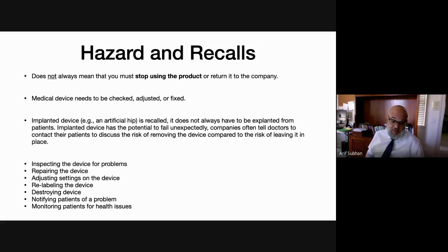So it's fine. If there's a problem, you go fix it. Then you need to repair it, maybe adjust it, or there may be an issue with a particular feature or particular program within that device. In some cases, the device has to be destroyed because it cannot be fixed and it's a danger to the patient. Sometimes, if it's in a patient, then you have to notify the patient of the problem, and you need to monitor the patient for any health issues, because if somebody has an artificial hip or an artificial valve or something of that nature, it's not like you can just go there, put your hand in and remove the device.